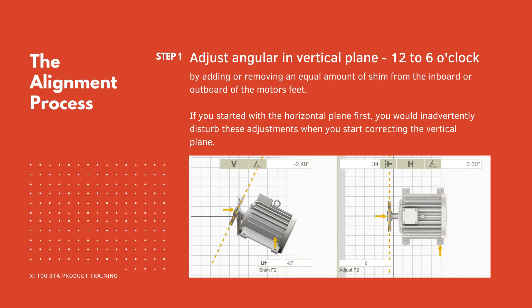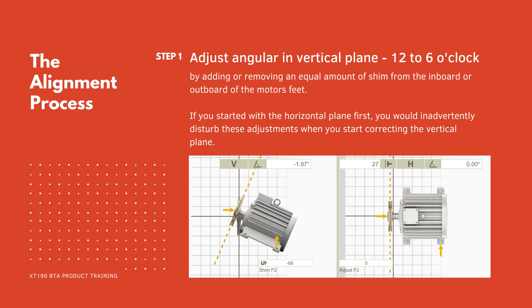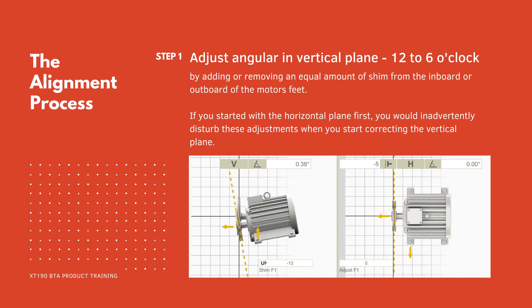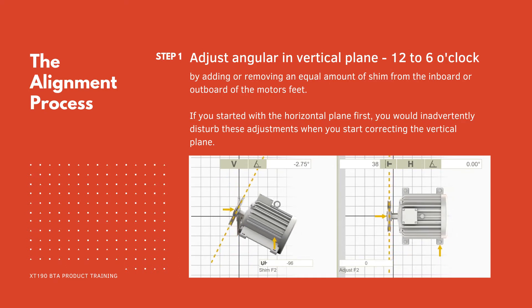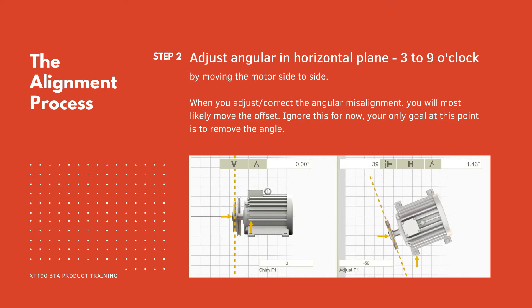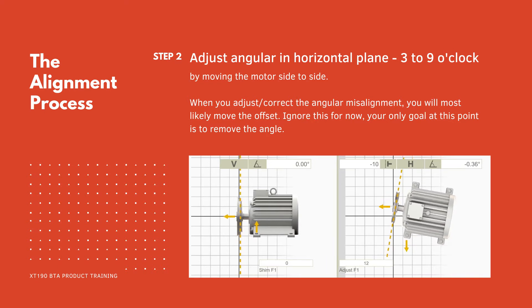Regardless of your alignment tool, the alignment process for shaft alignment should follow the same procedure. Step 1: adjust angular misalignment in the vertical plane — 12 to 6 o'clock — by adding or removing an equal amount of shim from the inboard or outboard of the motor's feet. If you started with the horizontal plane first, you would inadvertently disturb these adjustments when you start correcting the vertical plane. Step 2: adjust the angular misalignment in the horizontal plane — 3 to 9 o'clock — by moving the motor side to side. When you adjust the angular misalignment you will most likely move the offset; ignore this for now. Your only goal at this point is to remove the angle.